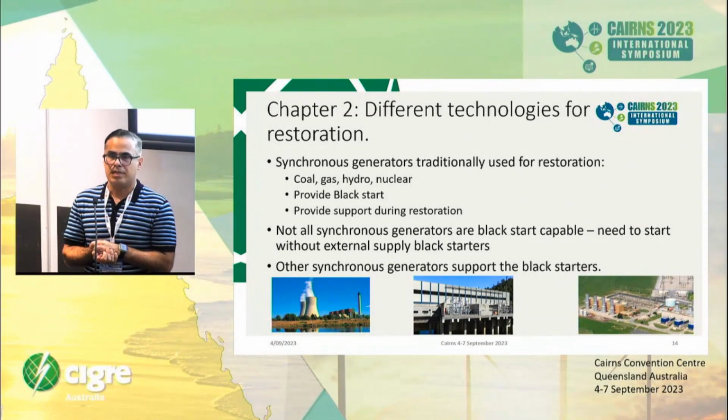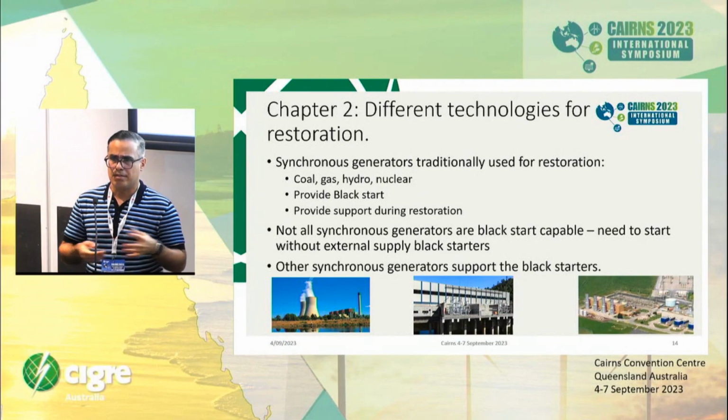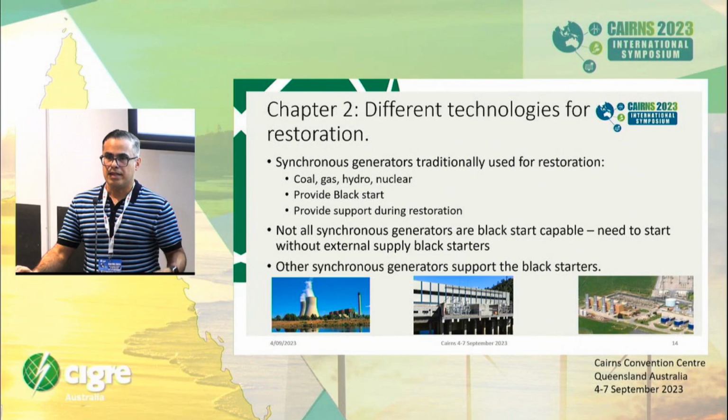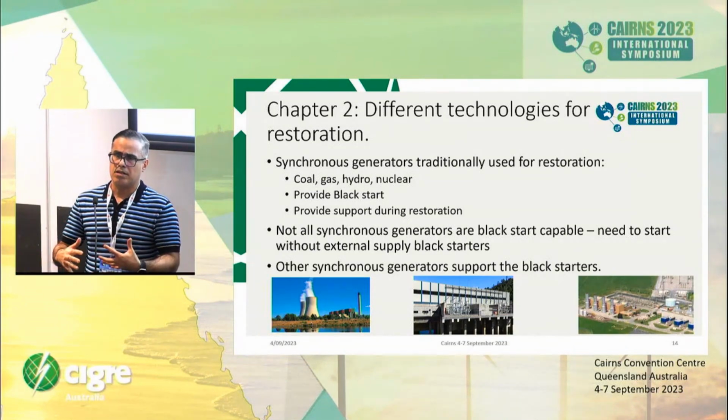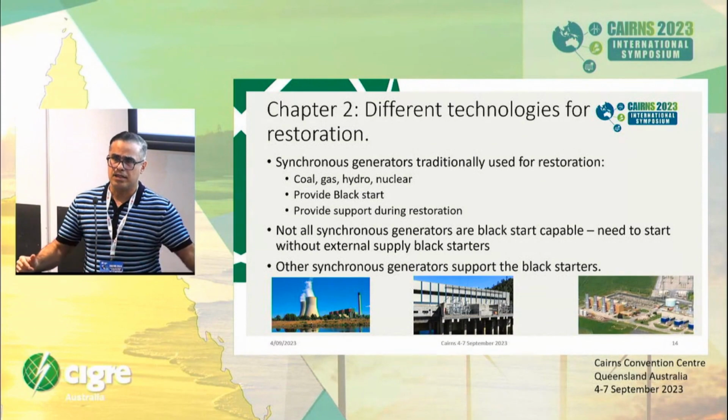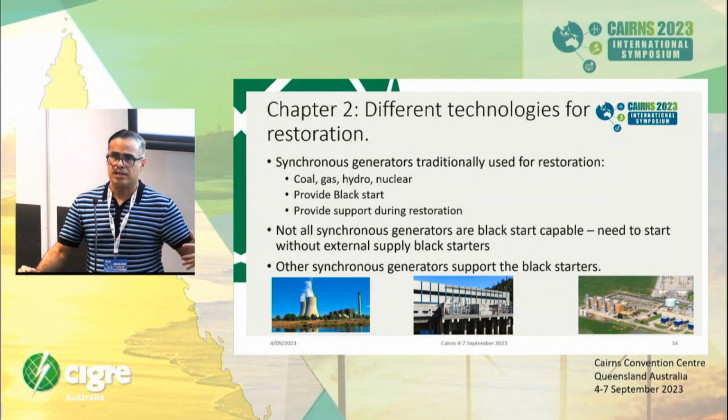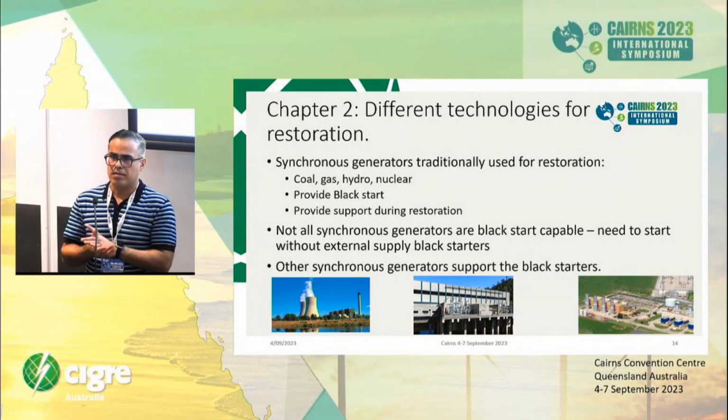Even with such an approach, there has been concern, and we have presented real examples, that the relay was not able to operate correctly, or disconnected the incorrect part of the system, and that's with a synchronous dominated power system.